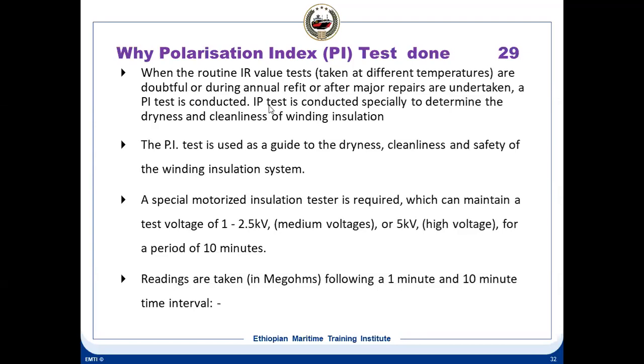For this, you need a 5000 volt Megger. You can use a normal Megger, but then you need a stopwatch to take the readings at 10 minutes and 1 minute. Some Meggers have a PI test facility. In that, once you select PI test, it will automatically read for 10 minutes, then read for 1 minute and give you the reading. So this is possible with a normal Megger, or a Megger which has a PI facility.